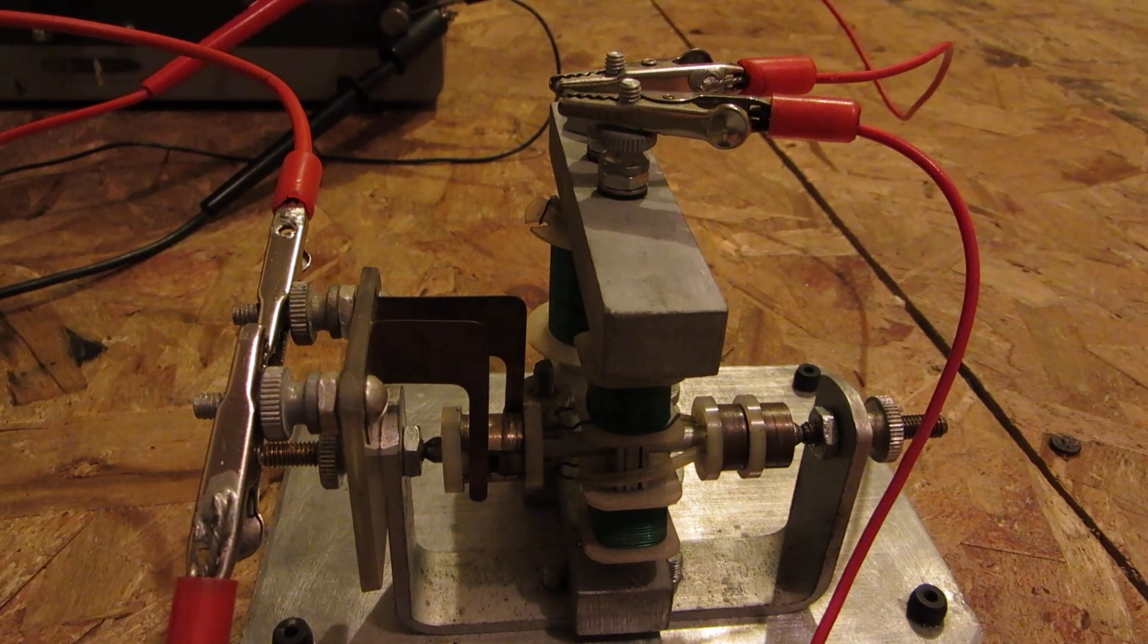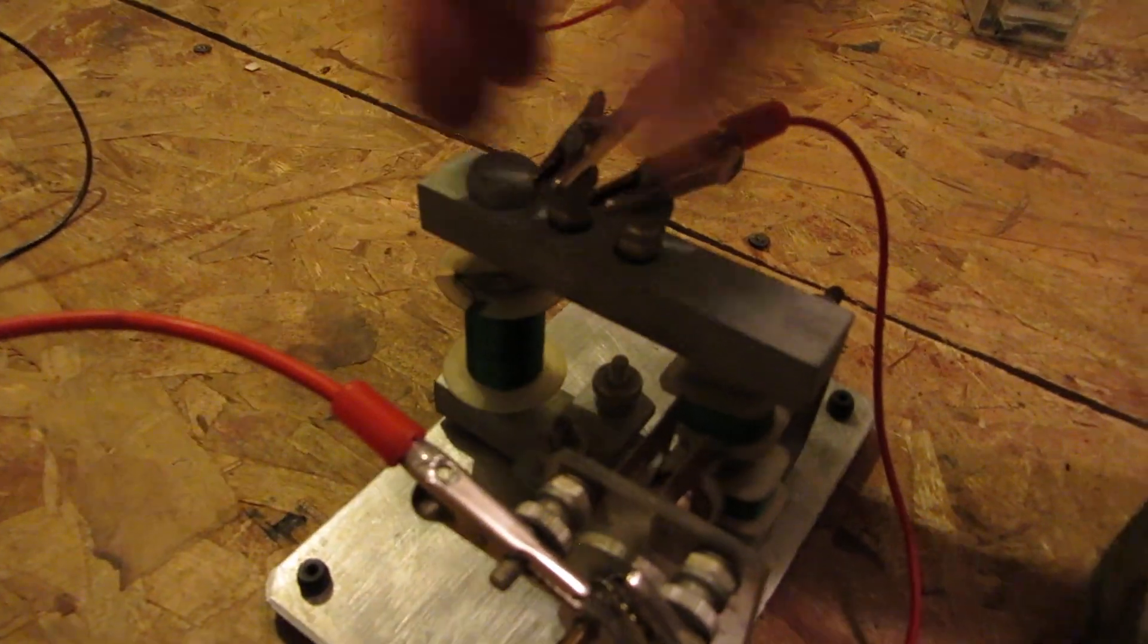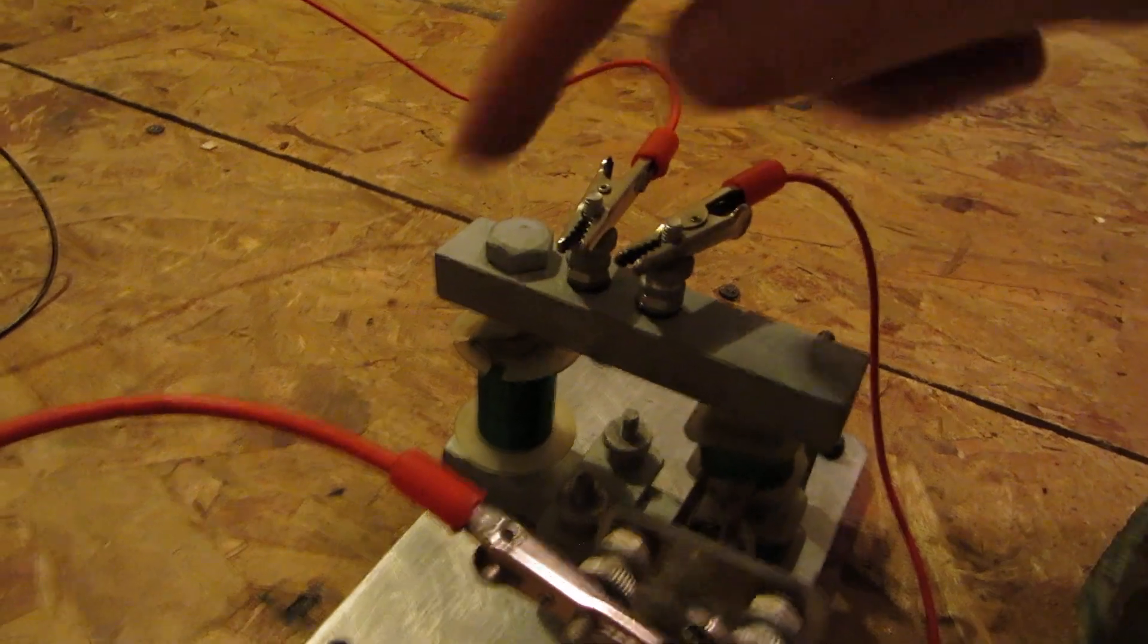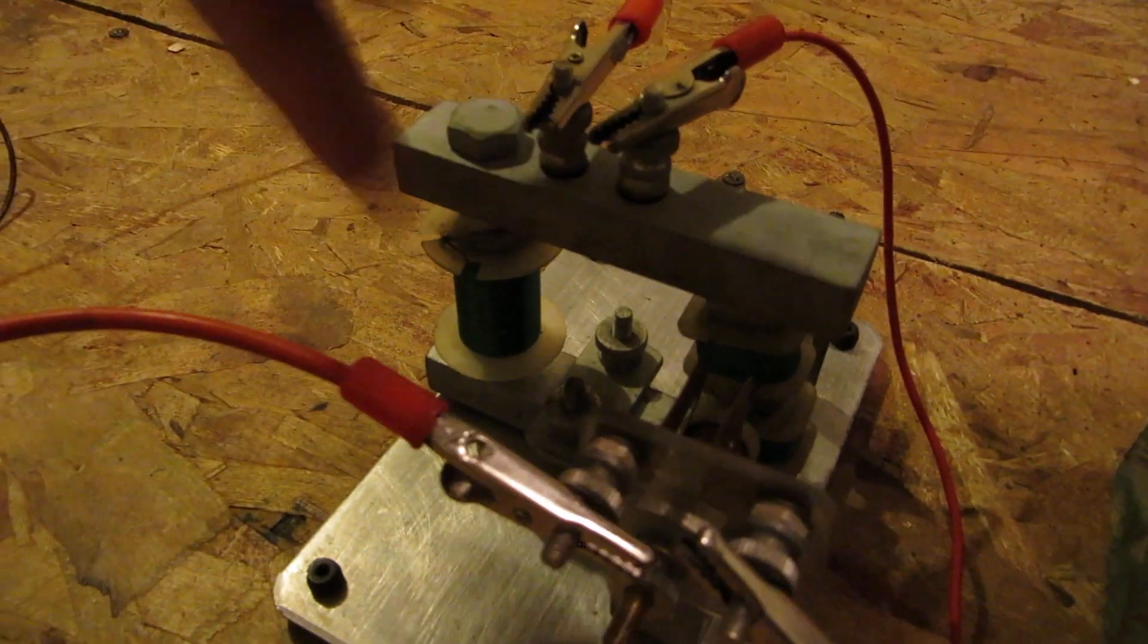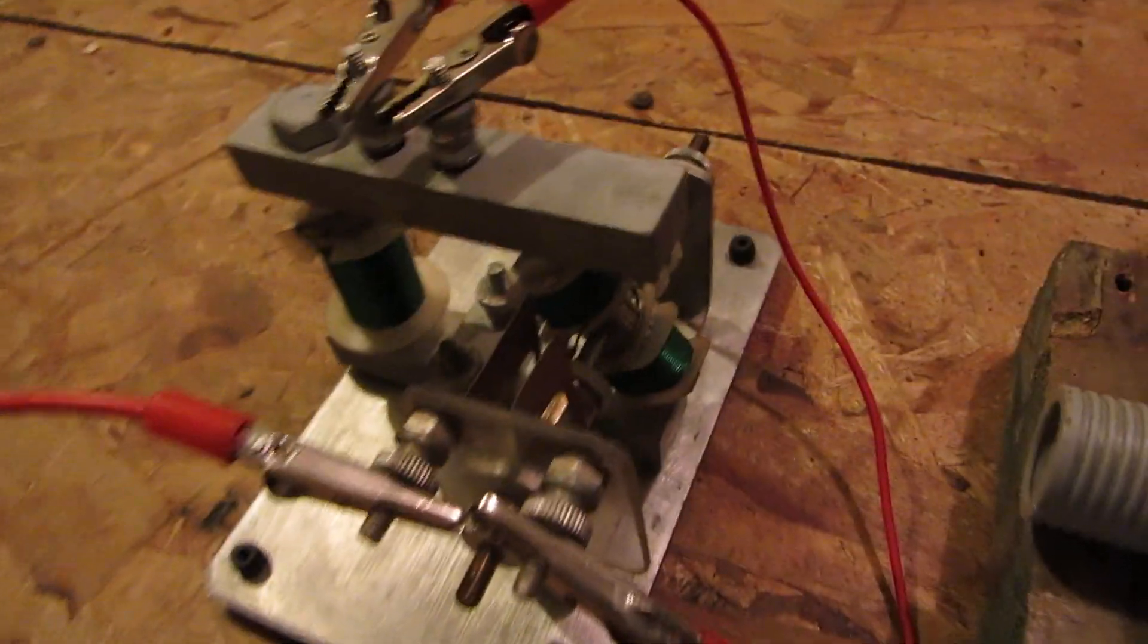So as I said with this one, it's not a permanent magnet, so you do have to energize it. So your power comes in. These two are for your field winding. And so it goes in, it spins around, it comes out, it goes through here. That goes to one brush, it goes through the brush, it goes through these, then back out, and then back to the power supply.